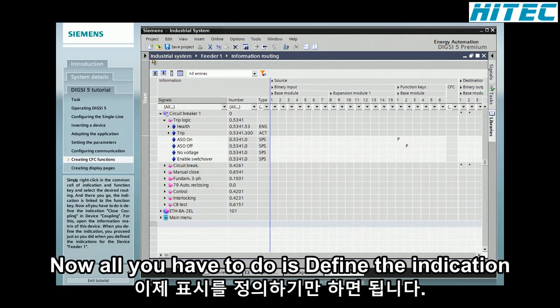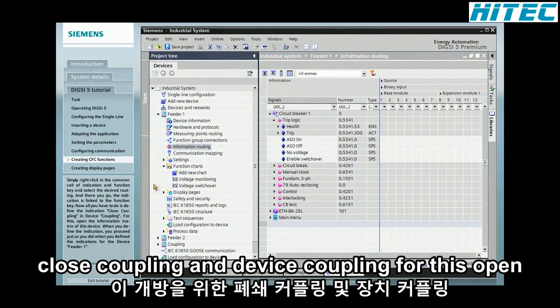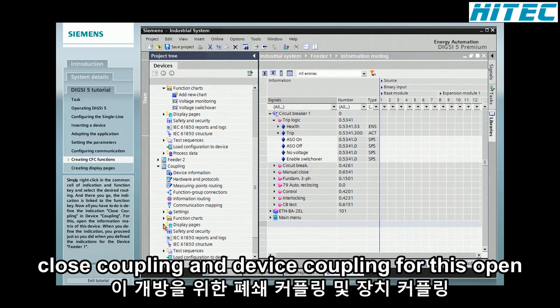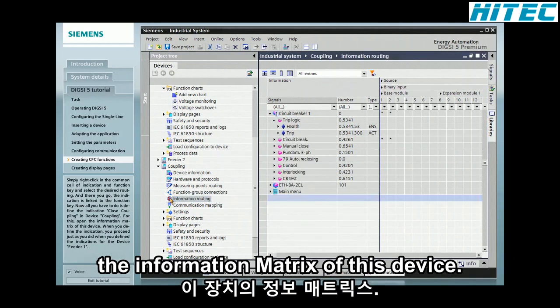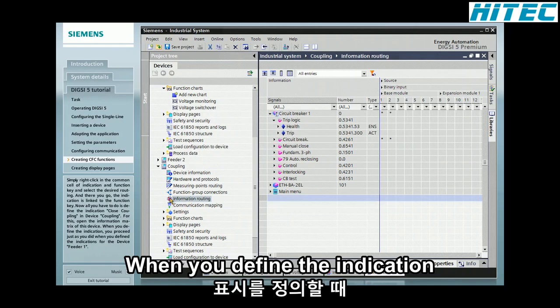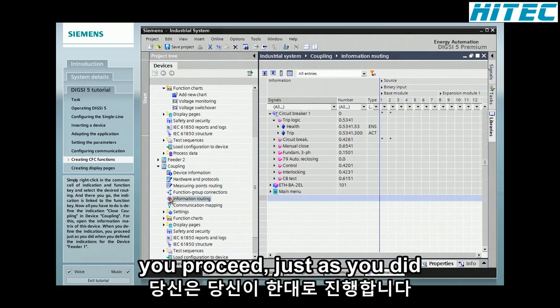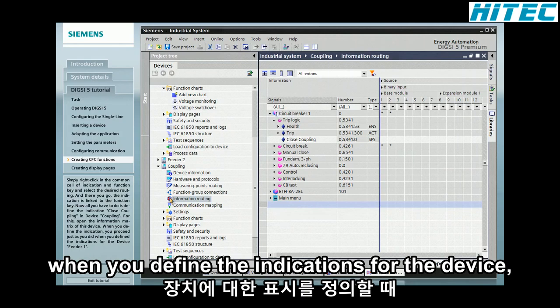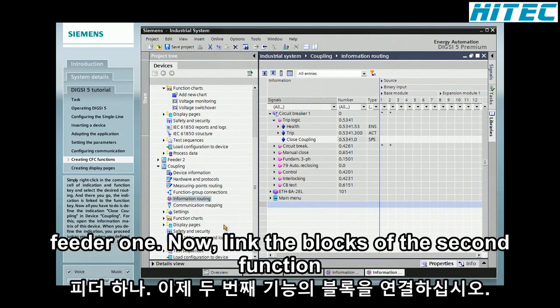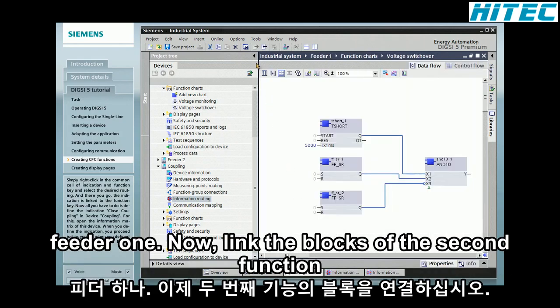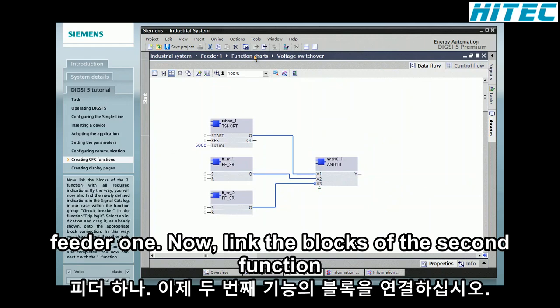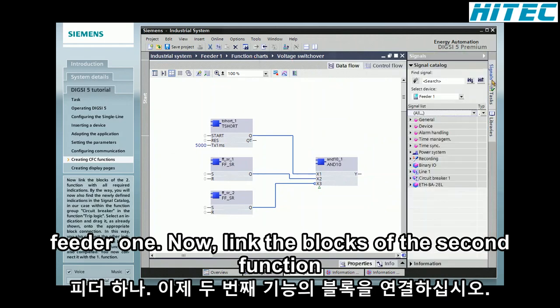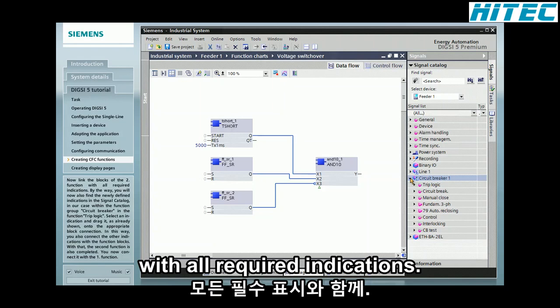Now all you have to do is define the indication close coupling in device coupling. For this, open the information matrix of this device. When you define the indication, you proceed just as you did when you defined the indications for the device feeder 1. Now link the blocks of the second function with all required indications.